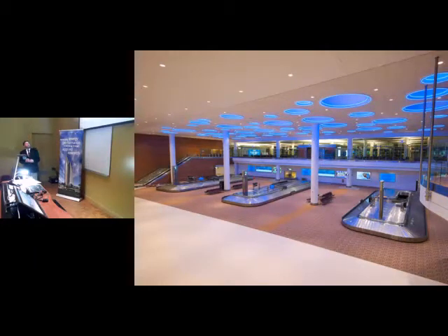If you look carefully in these baggage carousels, or when you're there in person, there's a series of openings in the top of them here. They're custom-made grills, the front and back. And basically we're pushing out cooler air at very low velocity but high volume from these openings in the top of the baggage carousels, spilling that air down along the floor and basically treating the lower 10 feet of the total volume of the space and not doing anything with the air up high.